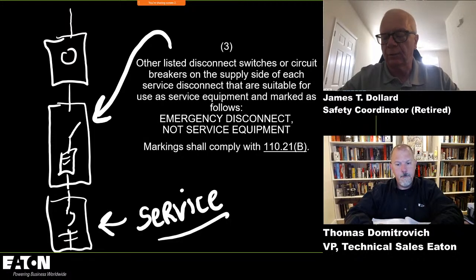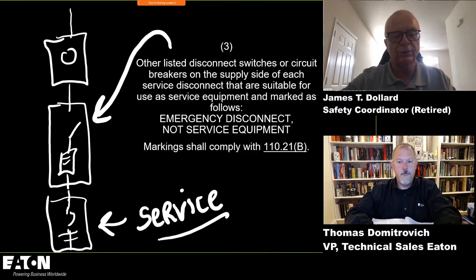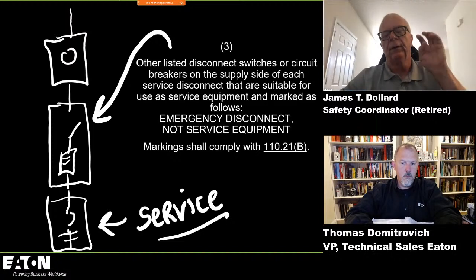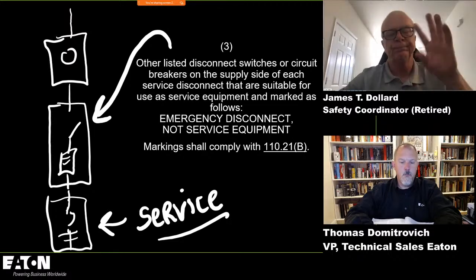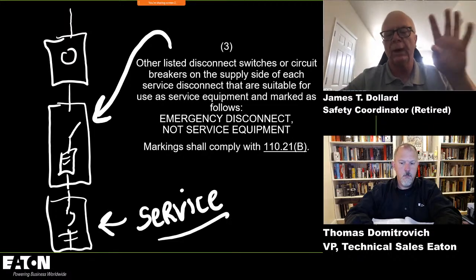Anybody that's been involved in the development and teaching of NEC standards, it's like baseball and apple pie. That first disconnect and overcurrent protection is your service disconnecting means, and everything downstream is a feeder or a branch circuit. Well, in order to make this feasible, we're going to permit you to have a listed disconnect, switch, or circuit breaker on the supply side of each service disconnect, as long as it's suitable for use as service equipment. The most popular way to get that done is going to be a meter housing with a 2-pole 100, a 2-pole 200, etc. That's the most feasible way to get it done.